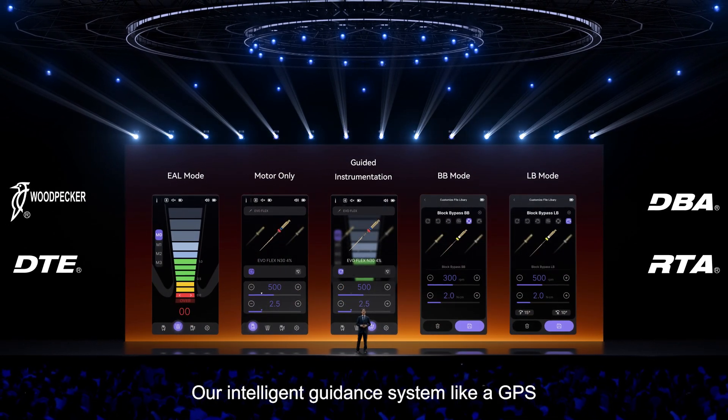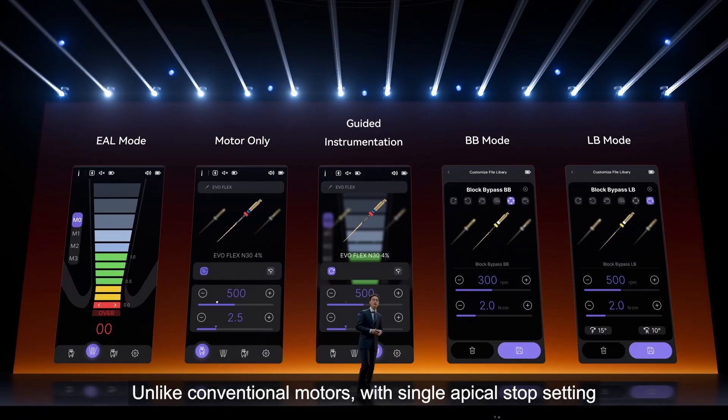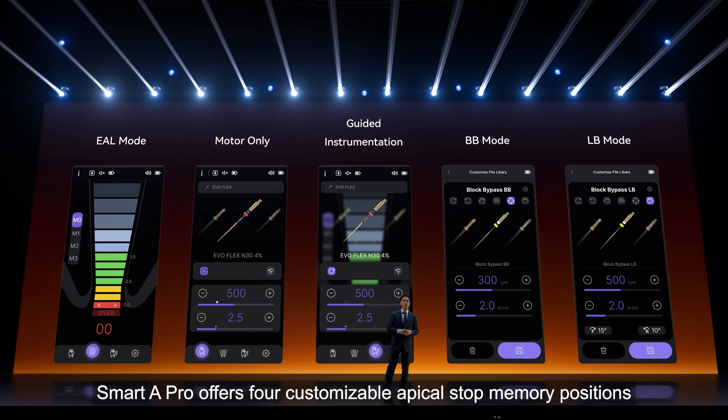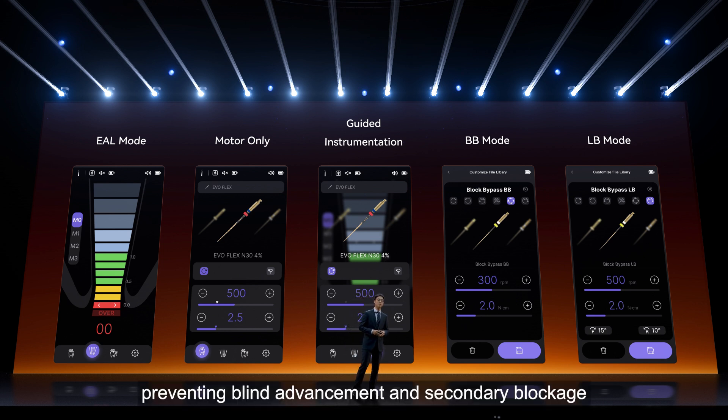Our intelligence guidance system acts like a GPS for your root canal treatment. Unlike conventional motors with a single apical stop setting, Smart A Pro offers four customizable apical stop memory positions. BB mode pauses every one second to allow debris evacuation, preventing blind advancements and secondary blockage.